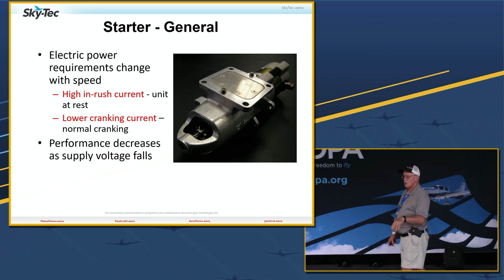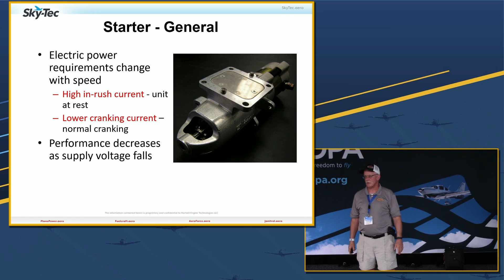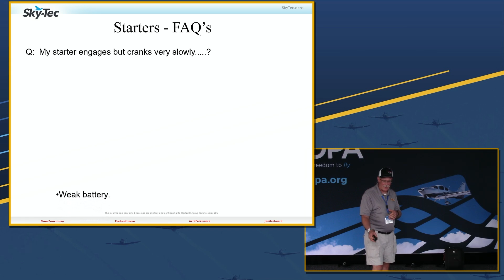For an intermittent load, you go to AC 43.13 - say it's running 5 feet, you've got an intermittent load, and that gives you the wire size to actually use. Simple route, been that way forever.